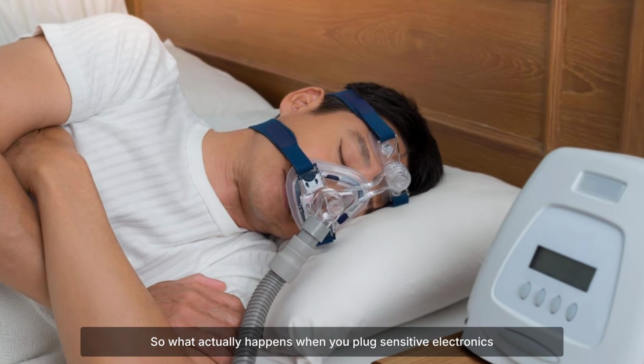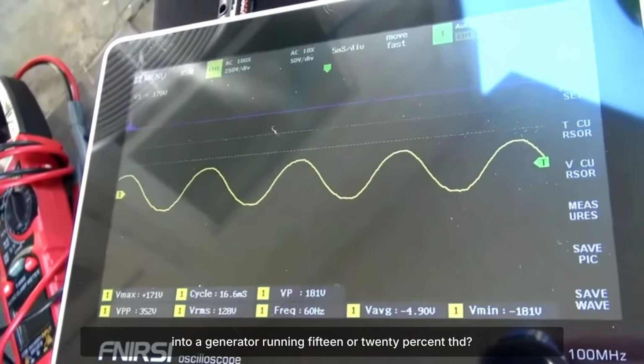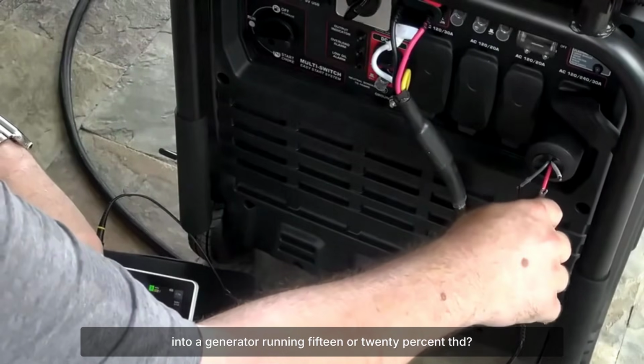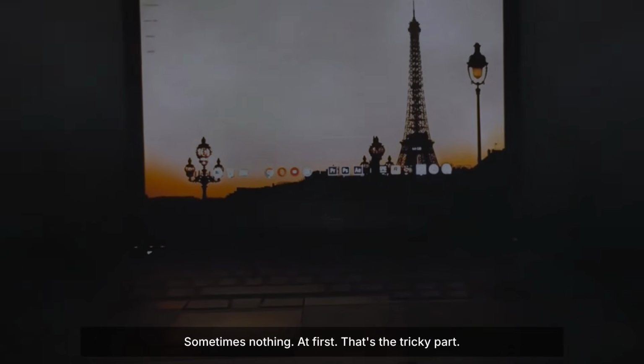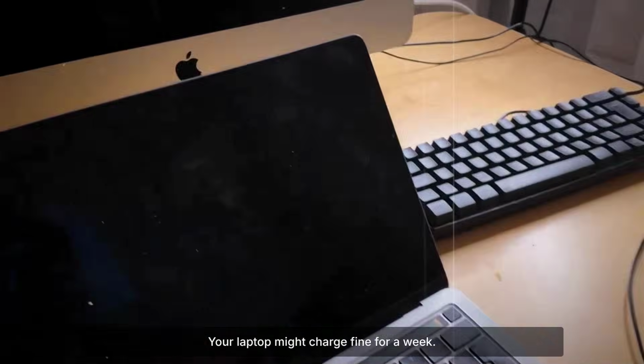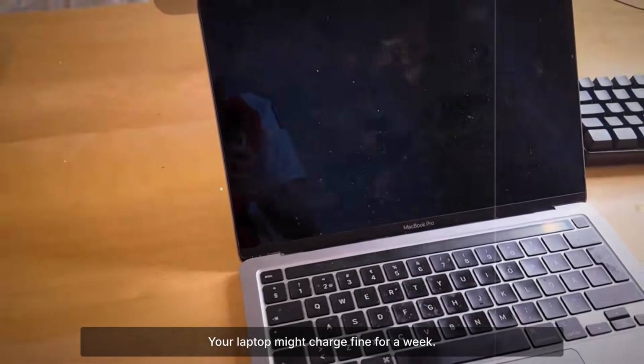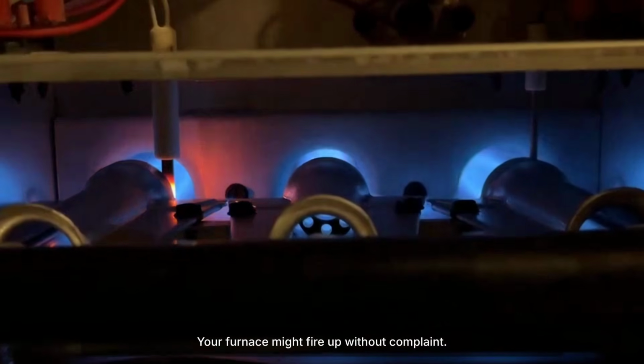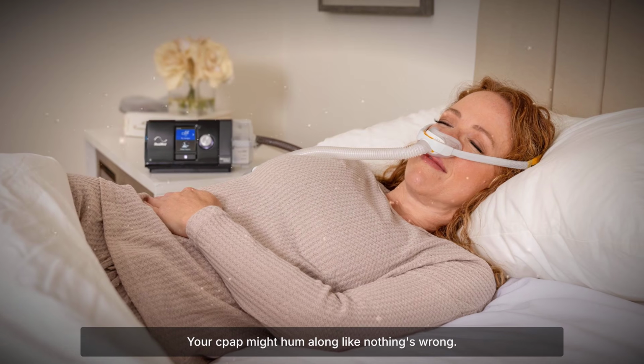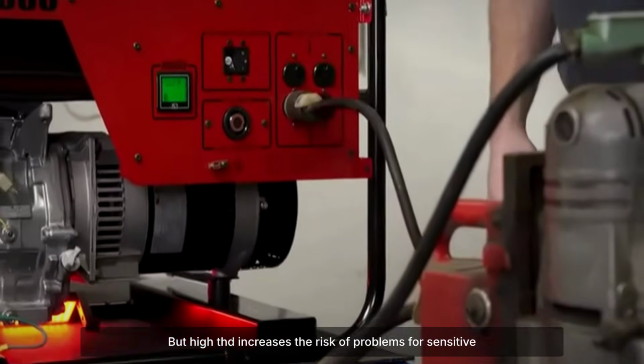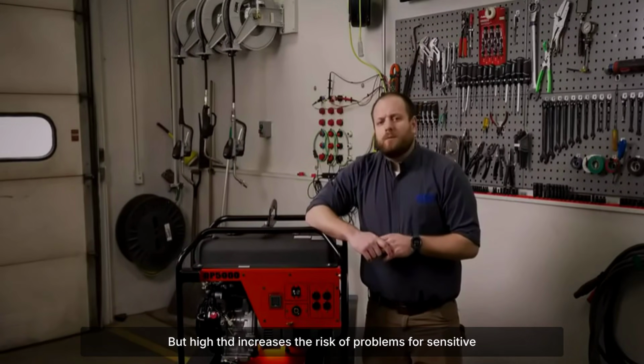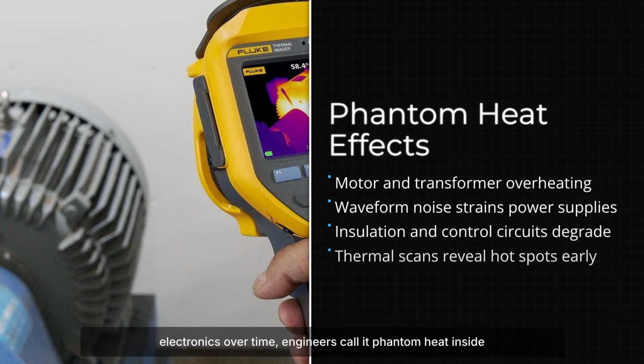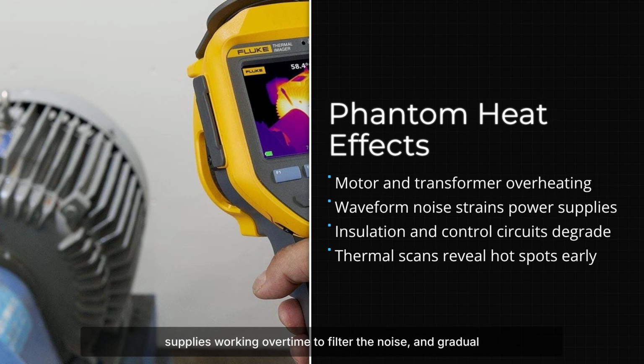So what actually happens when you plug sensitive electronics into a generator running 15 or 20% THD? Sometimes nothing. At first, that's the tricky part. Your laptop might charge fine for a week. Your furnace might fire up without complaint. Your CPAP might hum along like nothing's wrong. But high THD increases the risk of problems for sensitive electronics over time. Engineers call it phantom heat inside motors and power transformers, extra stress on power supplies working overtime to filter the noise, and gradual wear on insulation and control circuits.